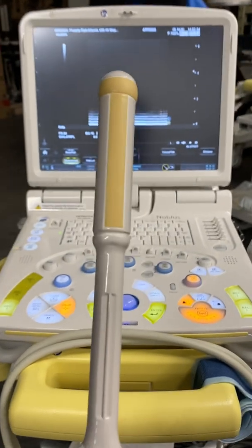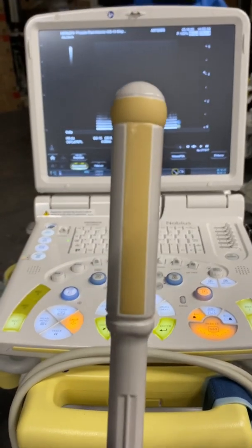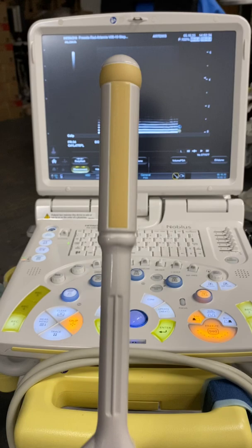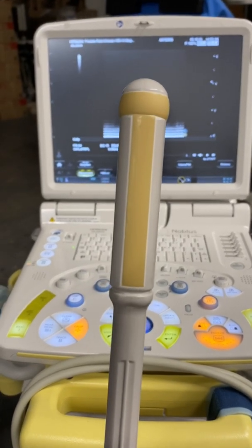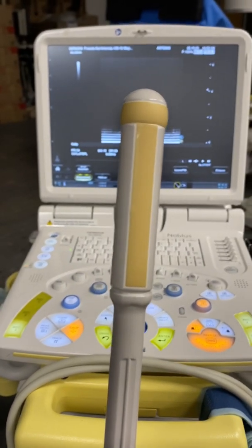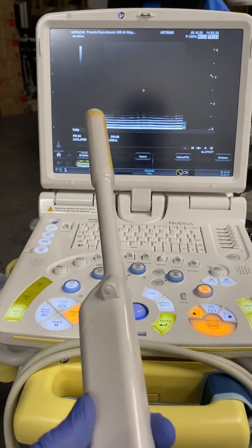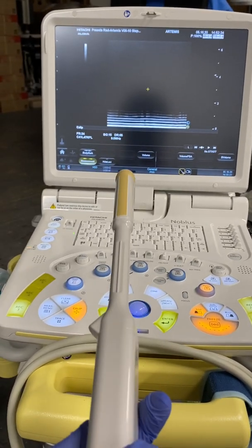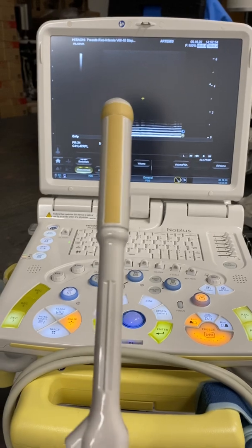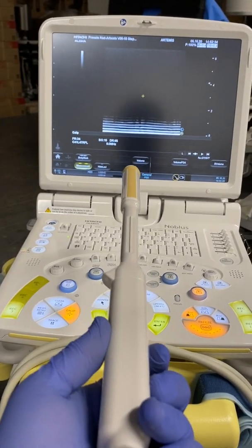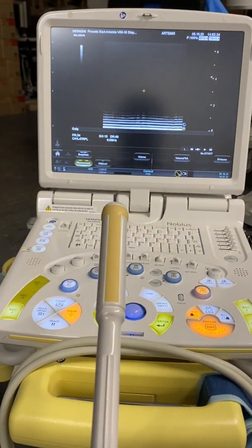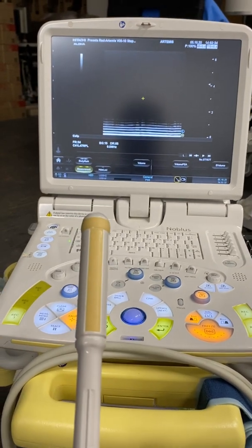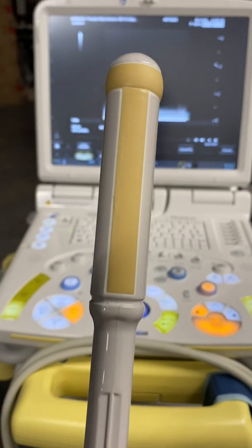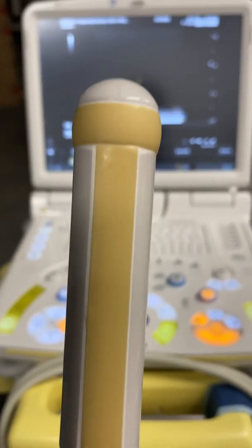So it's different from the other probe, the C41V, which we use for transrectal biopsy, in that with that probe, you can just turn the probe 90 degrees to see sagittal and then axial. This probe here stays in this position, and just by moving in and out, you put the gland over the crystal that you want to see. So if you want to see sagittal, you use this crystal. If you want to see axial, you use this crystal.